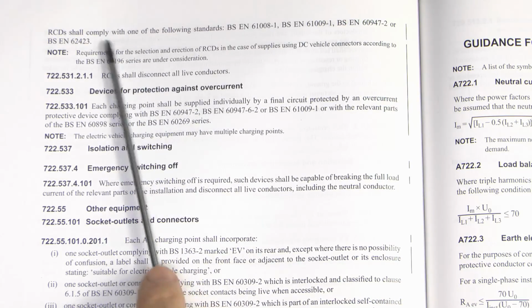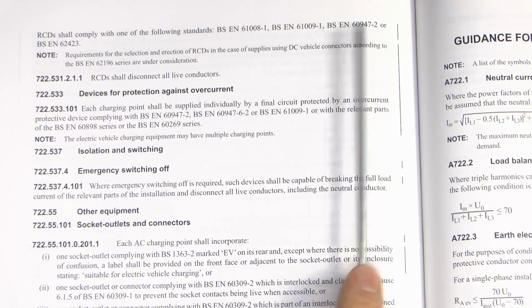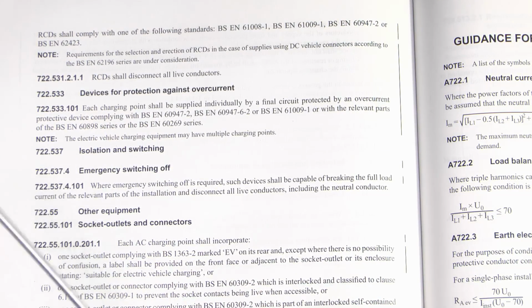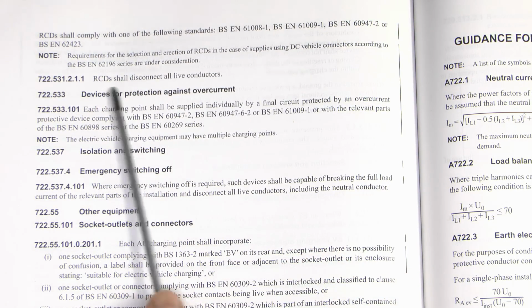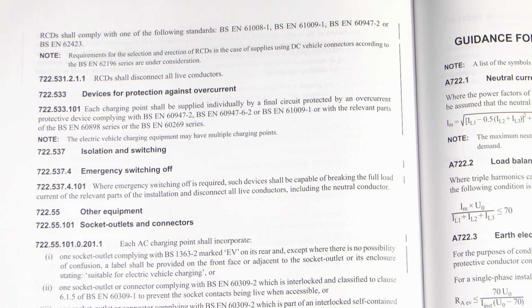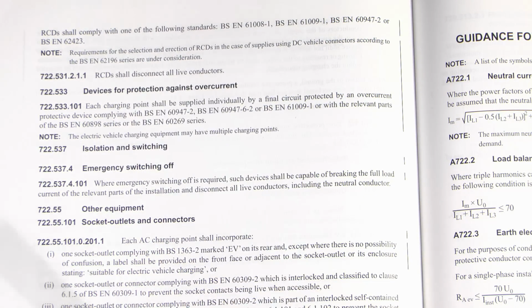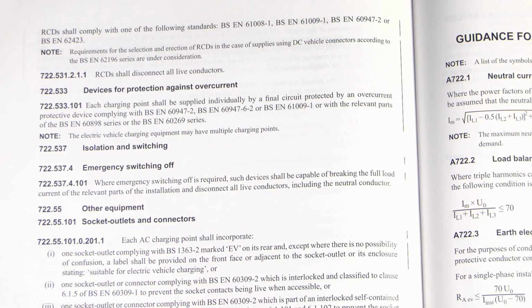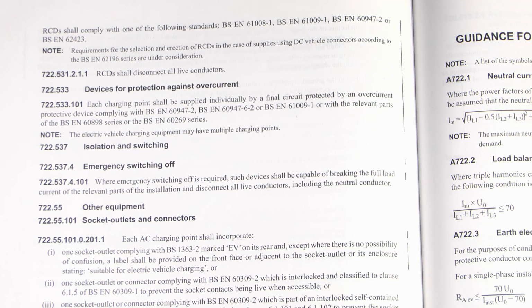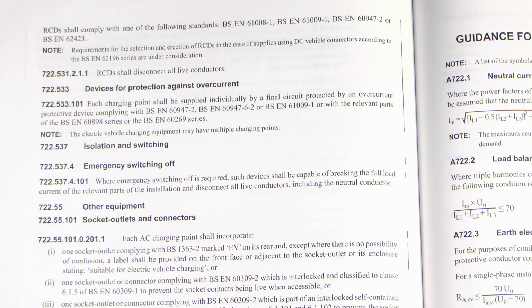And then over the page, the RCD shall comply with one of these following standards, which are basically the standards for RCDs, so no real surprises there, and it shall disconnect all live conductors, so again that's pretty much standard, just a two-pole RCD with line and neutral in the event of a single phase supply. So all pretty much standard stuff, but just be aware of the particular type of RCD that is required.